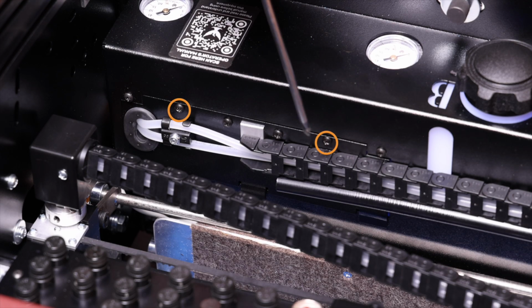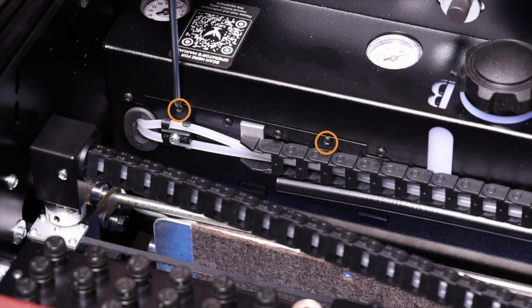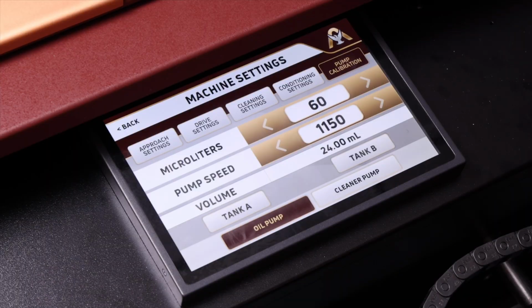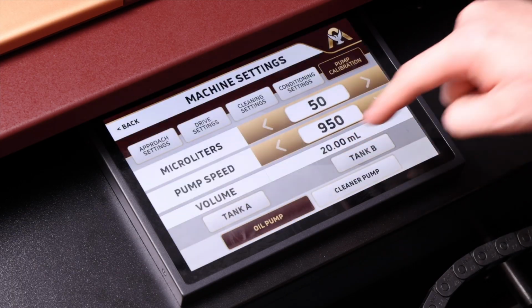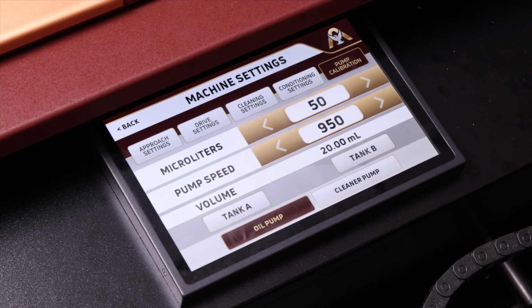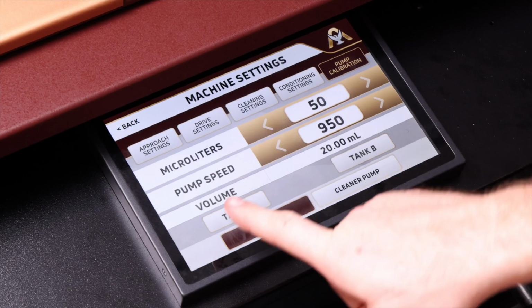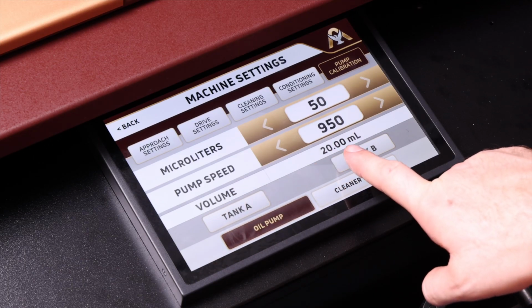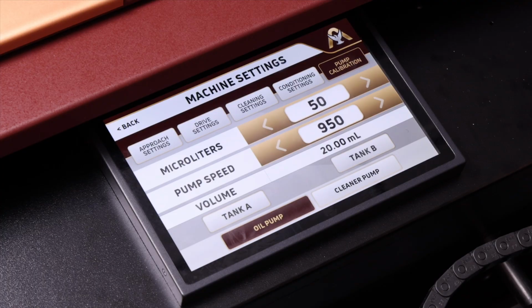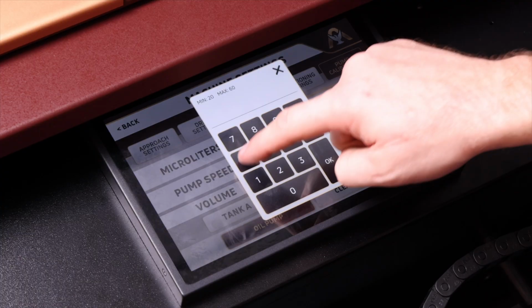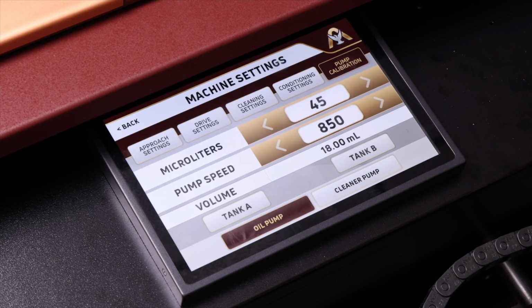Once complete, replace the hardware on the access plate and tighten in place. With the manual adjustment now made to our pumps, our max output should be correct. Most patterns are factory set to 50 microliters. If you were to run the test and you do not get the desired 20 milliliters, then we would need to make an adjustment from the screen. This would be done for any other microliter setting used in the desired pattern.